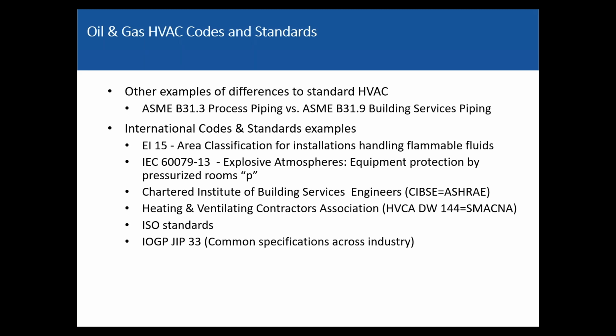On the international side, these are just some examples. EI 15, Energy Institute 15, is the international equivalent to API 500. IEC 60079-13 is the equivalent to NFPA 496. And then Chartered Institute of Building Services Engineers, CIBSE. That is the UK version of ASHRAE. And there's starting to be a lot of collaboration between the two. But when you do a design and you're international, here we'll say follow ASHRAE standards. Well, internationally you say follow CIBSE standards, or follow CIBSE or ASHRAE. It's very equivalent.